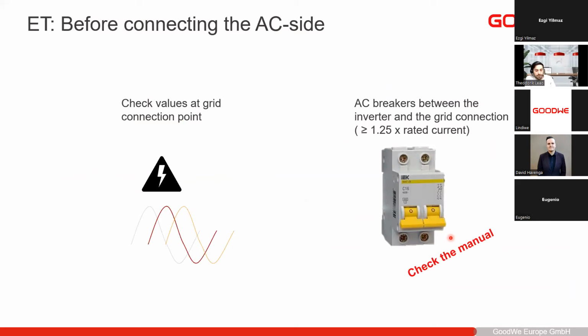We have now connected the DC side, we have connected the battery as well, and now it's time to connect the AC side. Before you connect anything on the AC side, please check the values at the grid connection point to make sure that you connect to the correct phase and that the grid is working properly. Secondly, please install AC breakers on the AC side, some kind of breakers before the grid connection, so that you can easily turn off and disconnect the inverter. It's recommended to have it 1.25 times the rated current of the inverter.